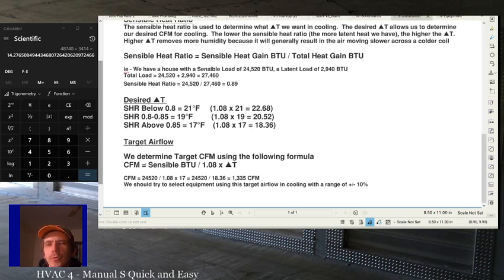But if you have seen a heat rise formula for calculating CFM, where you use the heat rise through your furnace or your electric heat to determine how much CFM the system is putting out, then this formula should look very familiar, because all we got to do is take out sensible, and we're talking about BTUs divided by 1.08. A lot of times I write it as output BTUs divided by 1.08 times delta T, and that's our heat rise formula. It's the exact same formula, but this is what we use to determine what CFM we want in cooling. Okay, so the fact that we have to use sensible BTUs is important, but these should always give you CFM. This is your equation for determining CFM based on BTUs and delta T.